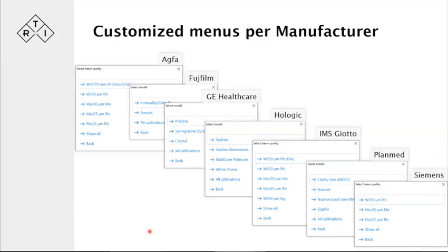So to make that choice a little bit easier, just looking at the beam qualities may not be as helpful. And the reason for us to have so many different calibrations is that we'd like to be as precise as possible when it comes to both kV and dose. The tolerances for dose are quite generous, so that's not too complicated, but the kV tolerances are tighter.